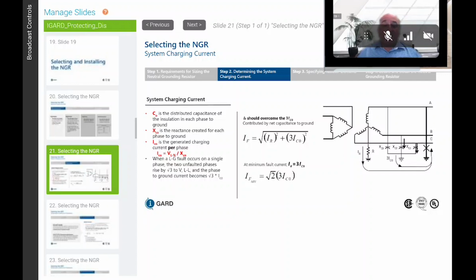So I_F can be a maximum of 7.07 amps if you limit your fault current to 5 amps and your charging current is 5 amps. And the maximum fault current at the point of fault is going to be 7.07 amps.